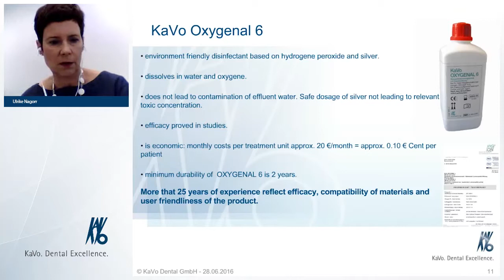In some situations, we are faced with the use of other disinfectants for the water. And here in this picture on the right side of the slide, you see what happens, for example, if chlorine-containing disinfecting agents are used instead of the Oxygenal. This can lead to corrosion of stainless steel parts, even involving the acrylic parts, and destroying materials.